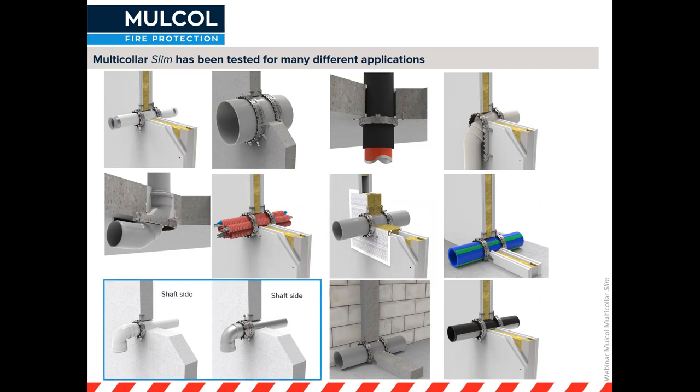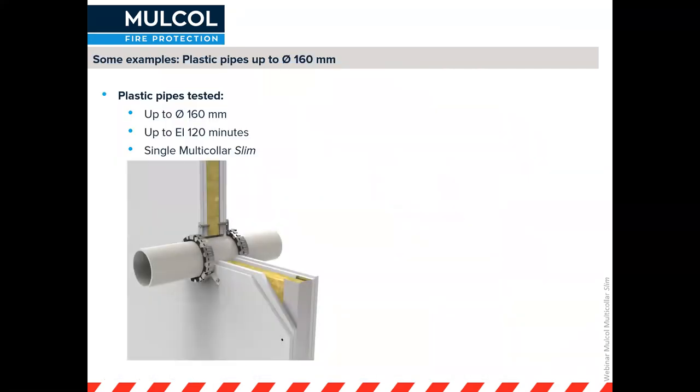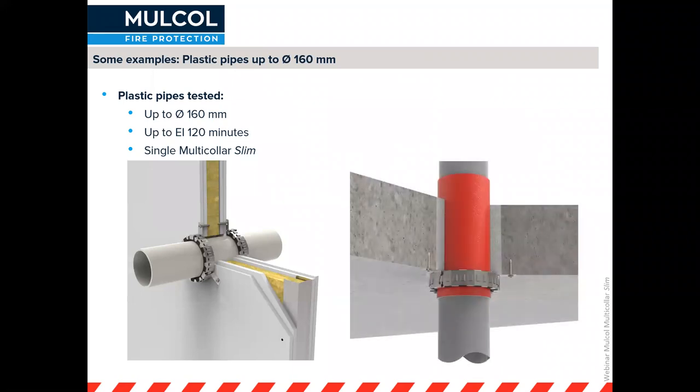We've also tested shaft hole situations with flue gas pipes, achieving 90 minutes for fire to the inside of the shaft. For pipes very close to a corner or close to the floor where you can't physically fit a full collar, we have solutions. For plastic pipes, with a plain single Multicollar Slim you can achieve up to 120 minutes, and tested through partitions — automatically also valid for rigid walls.